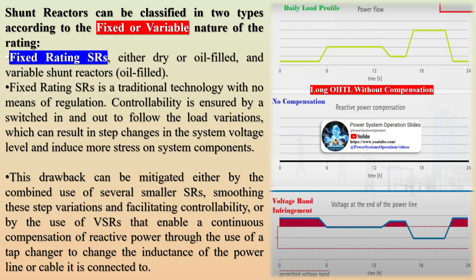This drawback can be mitigated either by the combined use of several smaller SRs, smoothing these step variations and facilitating controllability, or by the use of VSRs that enable continuous compensation of reactive power through the use of a tap changer to change the inductance of the power line or cable.